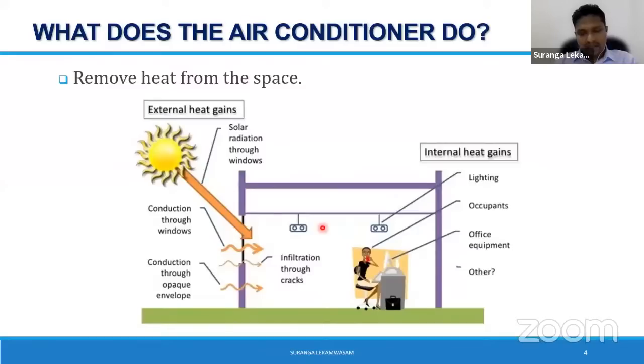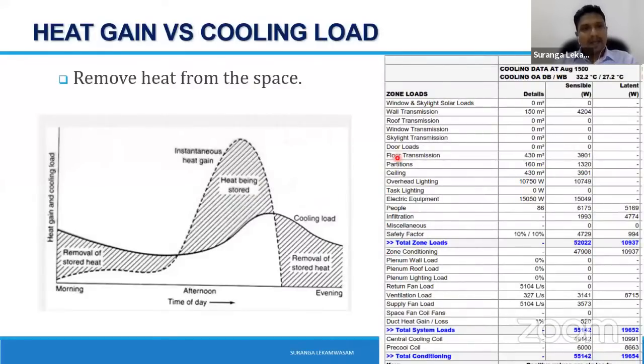But then I have a very humble question for you. Is the heat gain equal to the cooling load? Cooling load is the rate of heat removal. That is again an important thing which you must understand. Heat gain is not necessarily the same as cooling load, right? In most buildings, instantaneous heat gain and instantaneous cooling load are not equal. They are different simply because of the storage effect of the building. That is called the thermal mass or thermal inertia of the building. If you see the fundamental plot with time, the solid line shows your cooling load, whereas the dotted line shows your heat gain. You can see the heat gain is different, the cooling load is different.